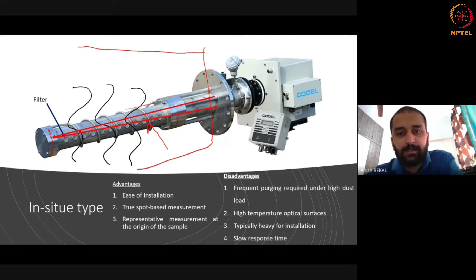And there is another type of installation also, where you have the analyzer kept safely at the bottom of the stack, and the stack will have a small probe, which is basically sucking the gas in, and then sending it through a sample line at a temperature of typically 160 degrees centigrade, so that no chemical reaction occurs. And then the analyzer itself can be placed very near to the control room or anything of that sort, where it would do the analysis. So many people prefer these kind of things, because the maintenance becomes very easy, because everything is on the ground. Only a probe is on the top, and the probe typically doesn't get choked that often.